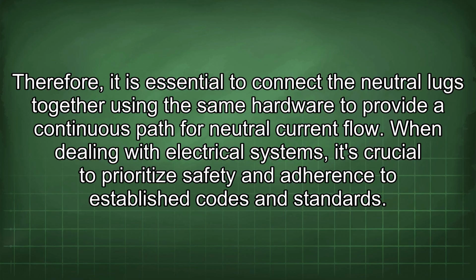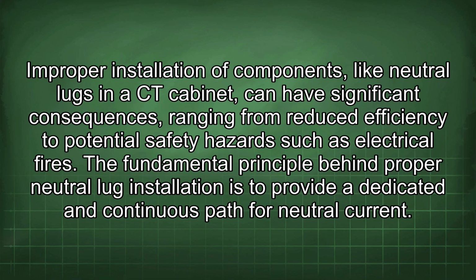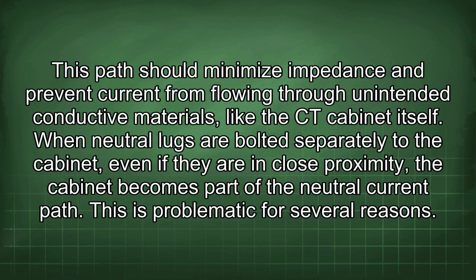When dealing with electrical systems, it's crucial to prioritize safety and adherence to established codes and standards. Improper installation of components, like neutral lugs in a CT cabinet, can have significant consequences, ranging from reduced efficiency to potential safety hazards such as electrical fires. The fundamental principle behind proper neutral lug installation is to provide a dedicated and continuous path for neutral current. This path should minimize impedance and prevent current from flowing through unintended conductive materials, like the CT cabinet itself.